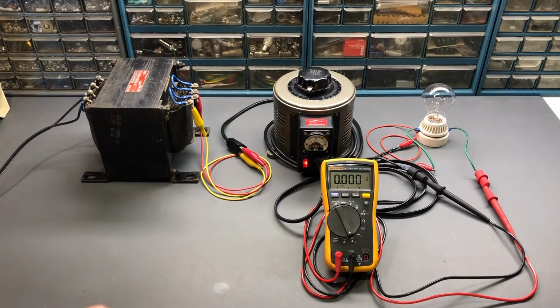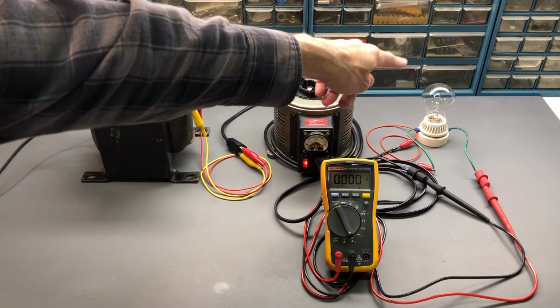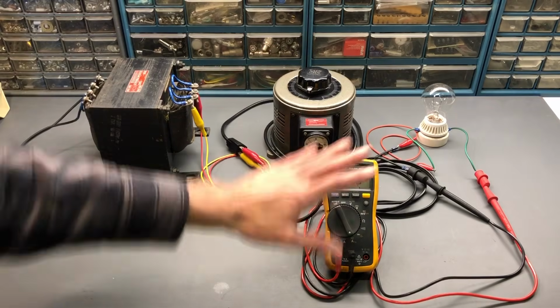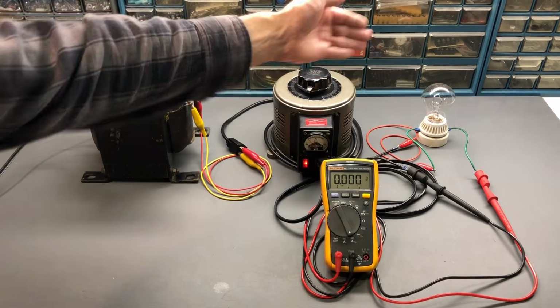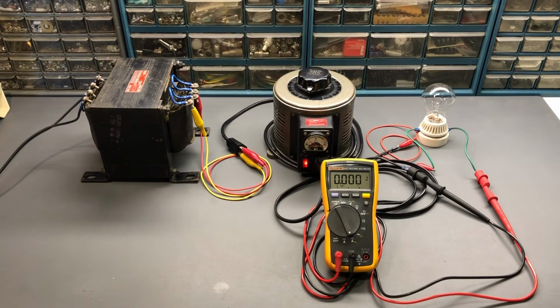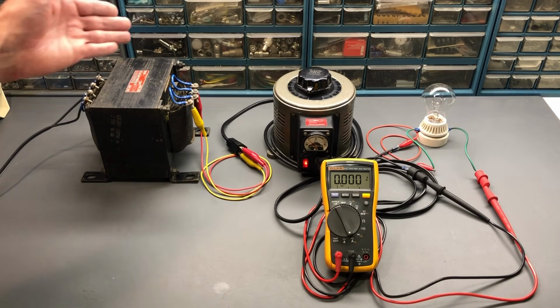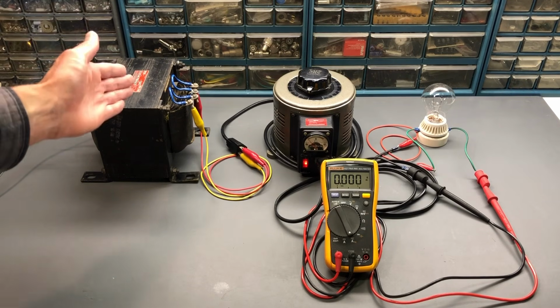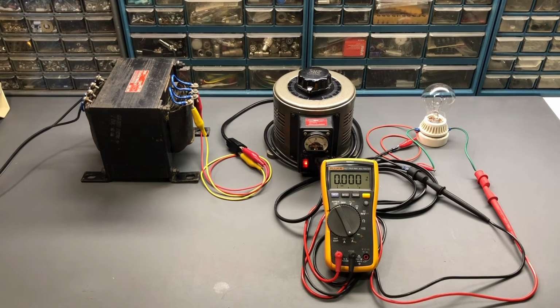So if we install a low wattage bulb over there and have no load connected and bring the voltage up, we have no indication on that bulb. It would remain off. The bulb is in no way affecting any voltage losses between the isolation transformer and the Variac, as we saw in the other demonstration. So my recommendation in building an isolated dim bulb tester is to use this layout. This works very, very well, and again, it's the one that I use on my bench.